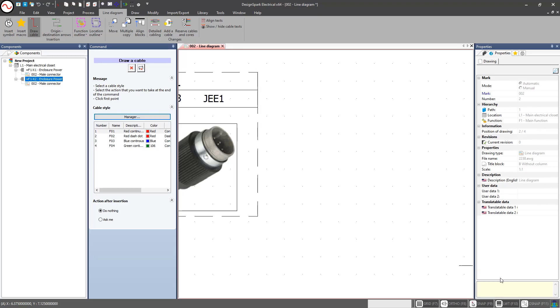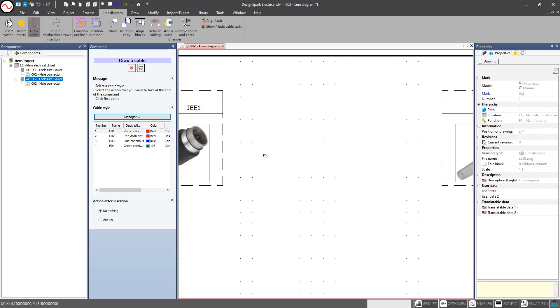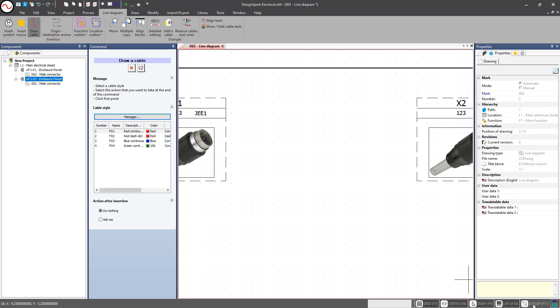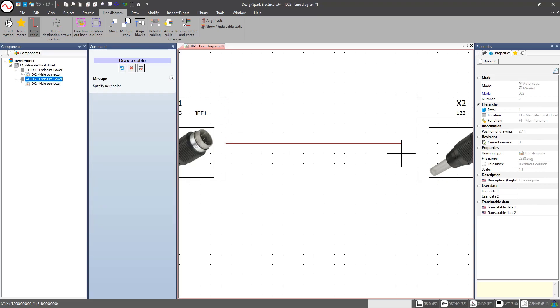One tip when working with line diagrams: I want to disable my object snaps. If you notice, I have my midpoint snap active, and I don't want to accidentally connect to that snap point instead of officially connecting between the two symbols. When you're trying to draw cables within your line diagrams, I recommend you turn off your O-snap. Down in the bottom right corner, simply select that, or press F11 to toggle it off.